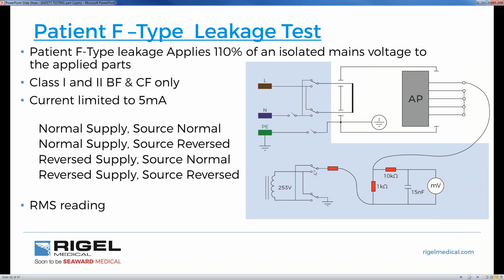For both BF and CF, bear in mind you wouldn't measure mains on applied part for a type B. It's only BF and CF. The reason why: B is earth referenced. If you put mains on anything that is earth referenced, then you're just going to get an inrush of current. So for obvious reasons, we just check BF and CF. I'll just go over that again. We put 110% mains voltage via a current limiting resistor through the body model onto an applied part. So we should have 25.5 volts at this point, and we want to prove total isolation between these applied parts, so we can say that no current is flowing back to protective earth.